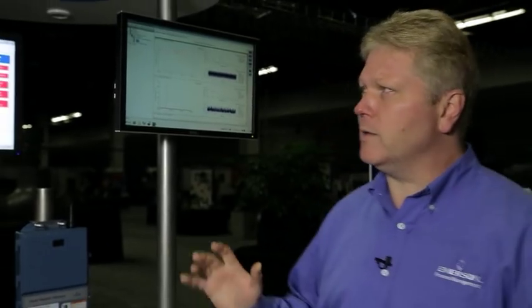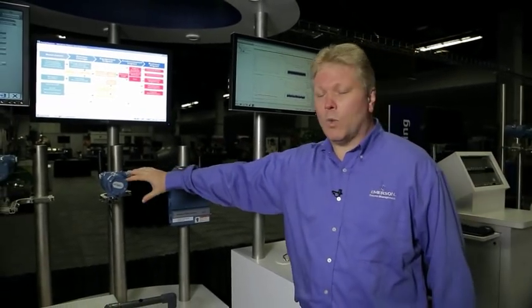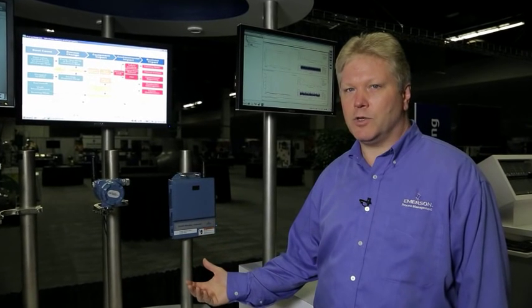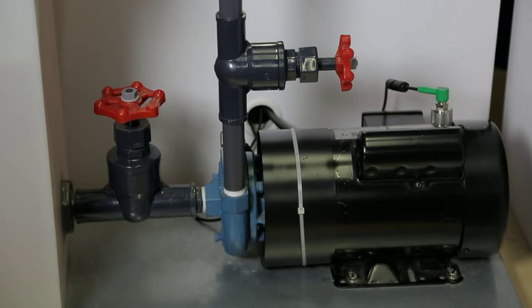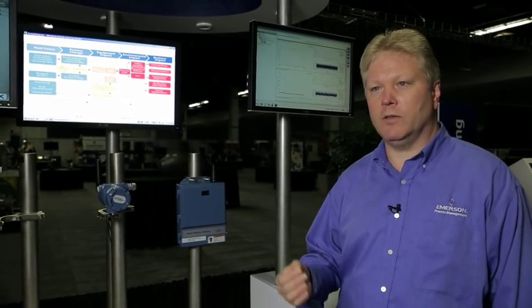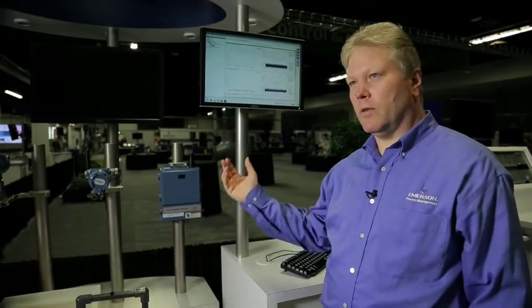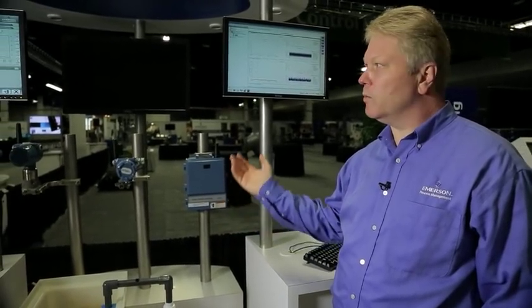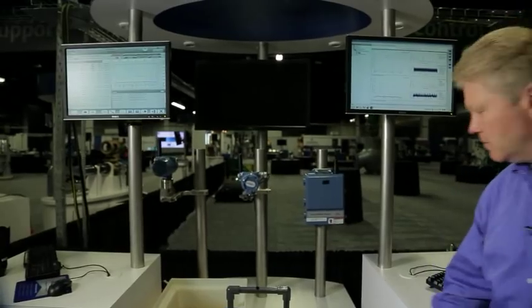The one key thing I would like to say is that our wireless vibration transmitter, the CSI 9420, has the overall vibration, but it also has Emerson's PeakVue. PeakVue really gives us a lot earlier detection of a problem going on in the pump. So there's time to take action, and that's a real benefit. Time to take action and prevent the failure. And now I'd like to show a demo of cavitating the pump, in which the higher vibration will send an alert to operations.